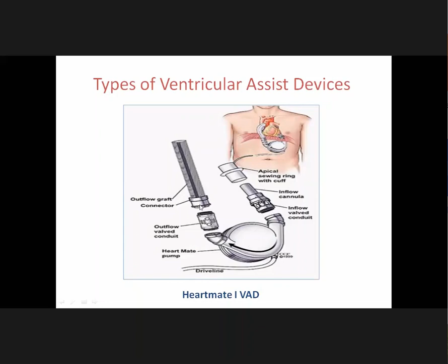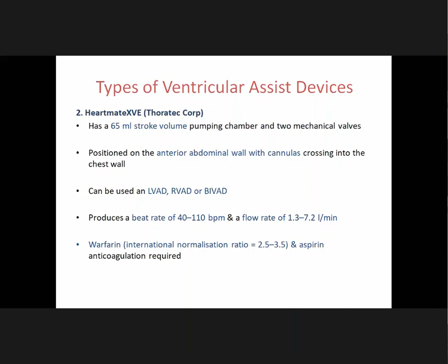The second one is HeartMate XVE, which has a 65 ml stroke volume pumping chamber with 2 mechanical valves positioned on the anterior abdominal wall with cannulas crossing into the chest wall. It can be used for the left ventricle, right ventricle, or both ventricles, and it produces a beat rate of 40 to 110 beats per minute with a flow rate of 1.3 to 7.2 liters per minute, and it requires continuous warfarin and aspirin anticoagulation with a target INR range of 2.5 to 3.5.